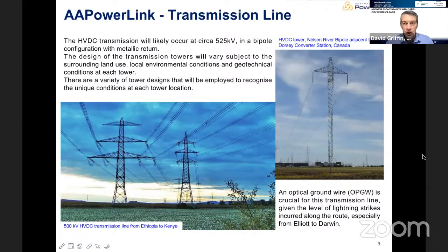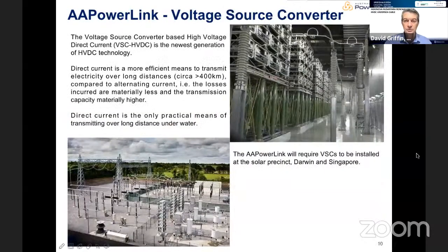The third element is the high voltage direct current system: the creation of links with voltage source converters, overhead and submarine cable transmission, and voltage source converters at the other end. For our system, we'll create a link from the solar farm to Darwin. A voltage source converter at the solar farm and one in Darwin will feed 800 megawatts of capacity into Darwin. There'll be a separate high voltage direct current link, meaning two voltage source converters in Darwin - one receiving power from the solar farm, and a second which is the start of the submarine cable link from Darwin to Singapore.